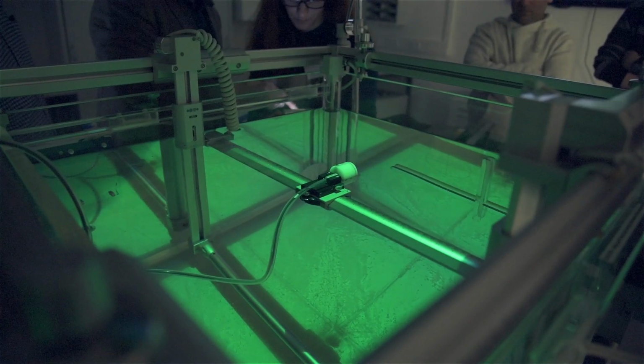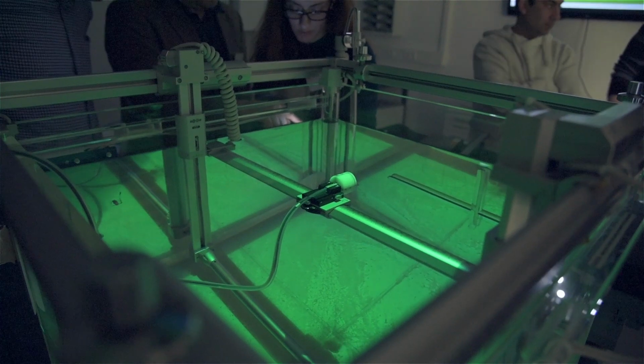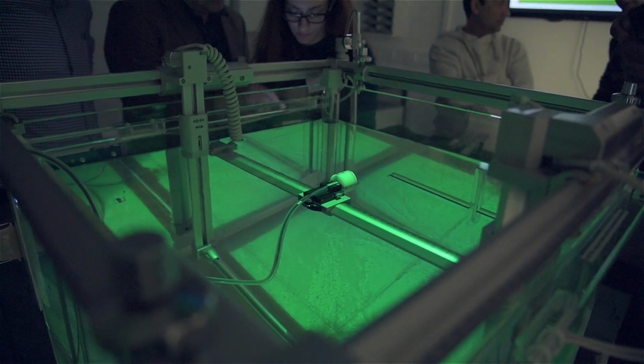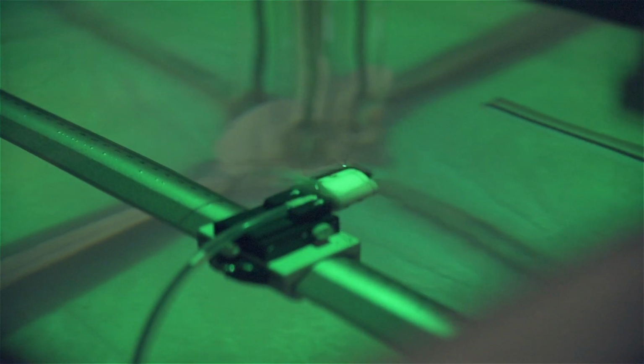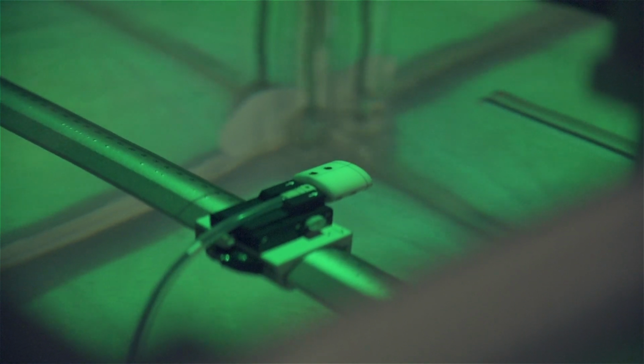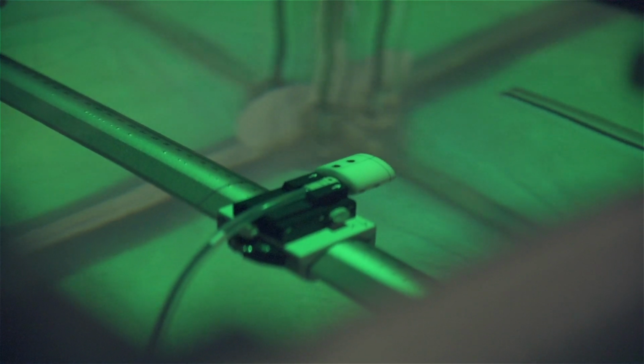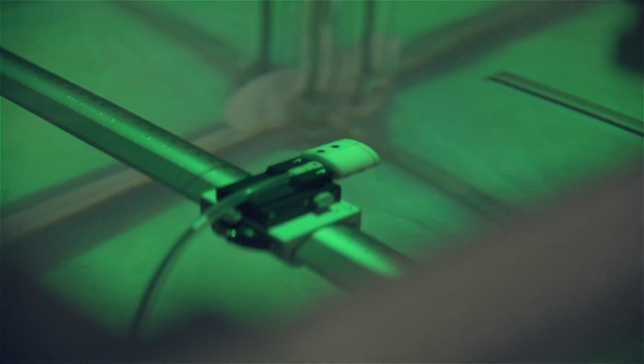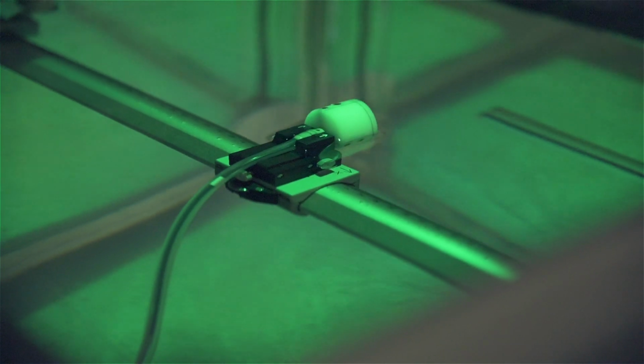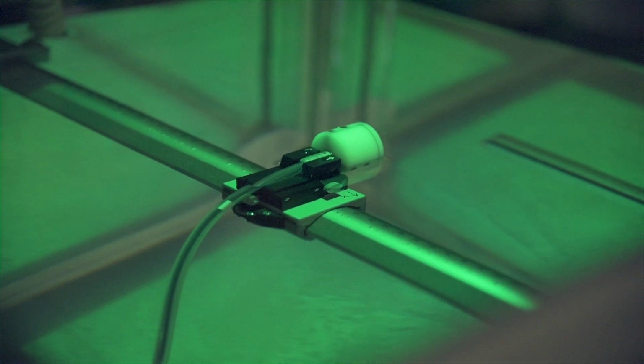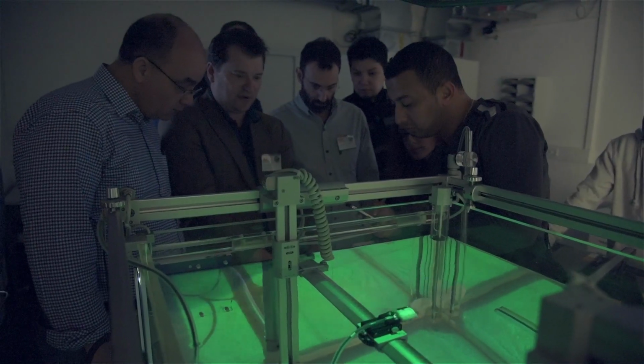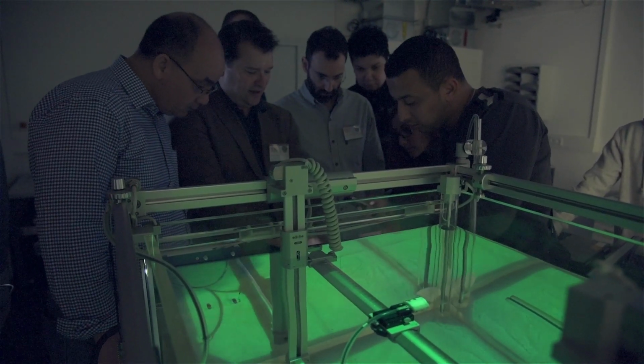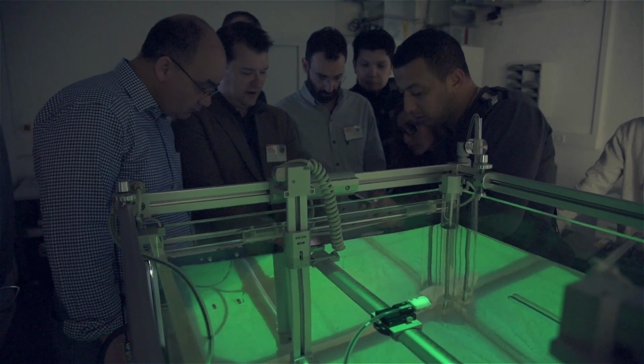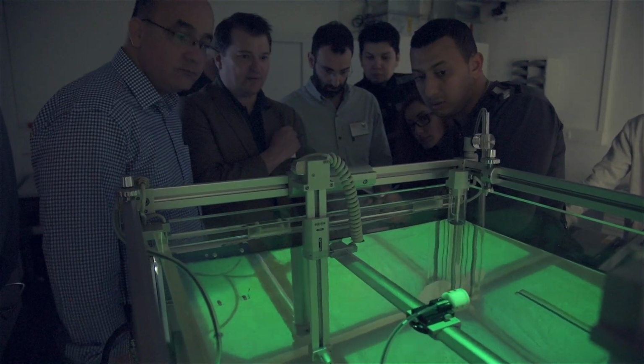Now this first button that looks like a bullseye down in this corner. Like a target. Press that button to go to the ISO center. So tell it to go to ISO center. Okay, and then the green arrow. Go. And it did it. It went back. Doesn't matter where, just a little bit. Then you select that one, and the green arrow means go, and it should return back to where it saved that initial position.